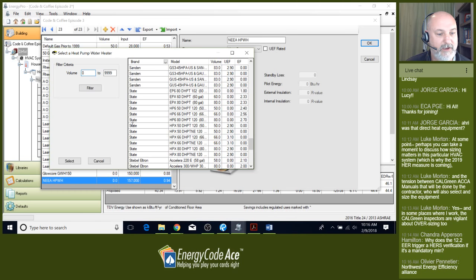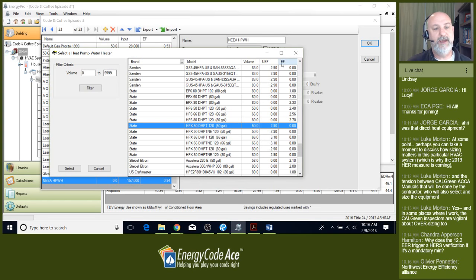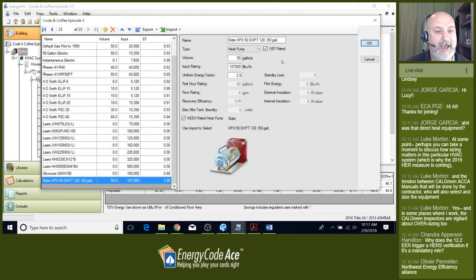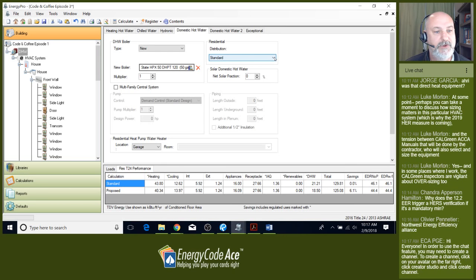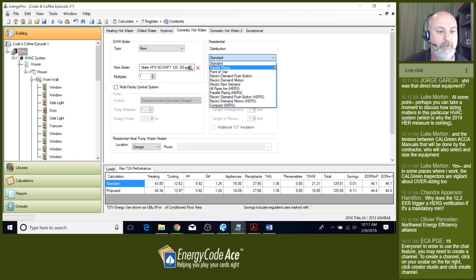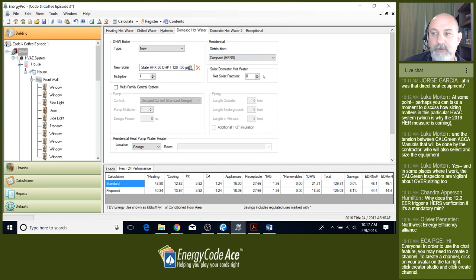Let's also do a compact hot water distribution credit. From the residential compliance manual, chapter 5 under section 5.6 Distribution Credits, we're looking at compact verified compact design. The premise is limiting the distance of the hot water piping based on the size of the house. Based on table 5-10, we limit the pipe run distance from the heat source based on house size.